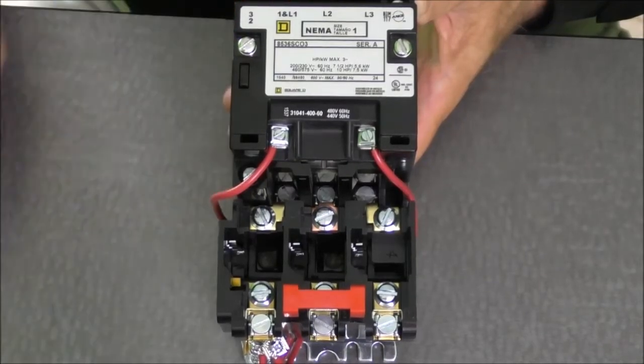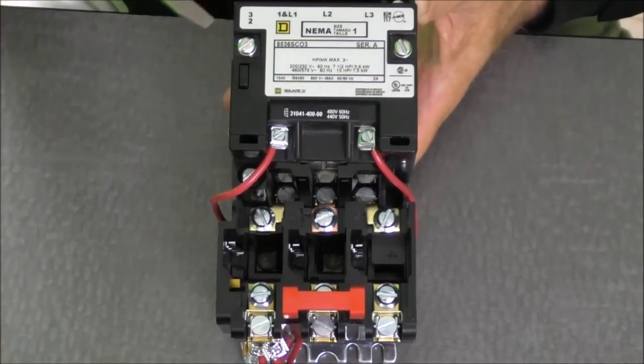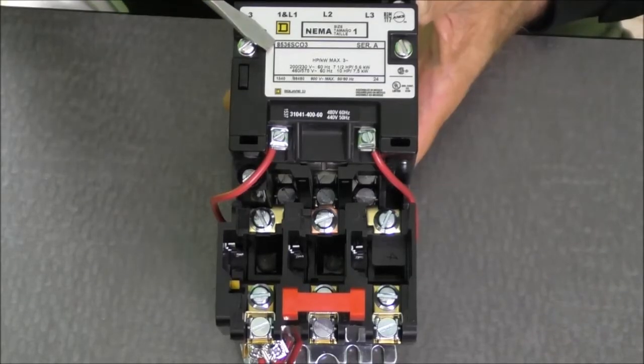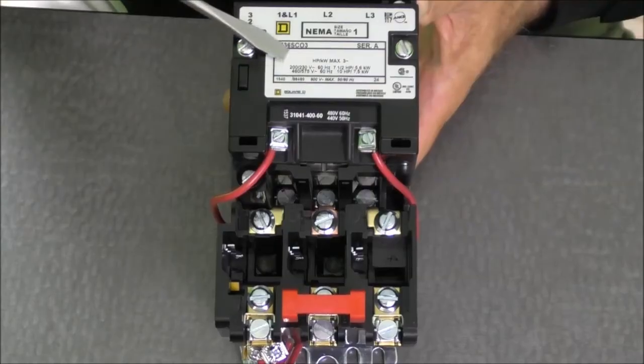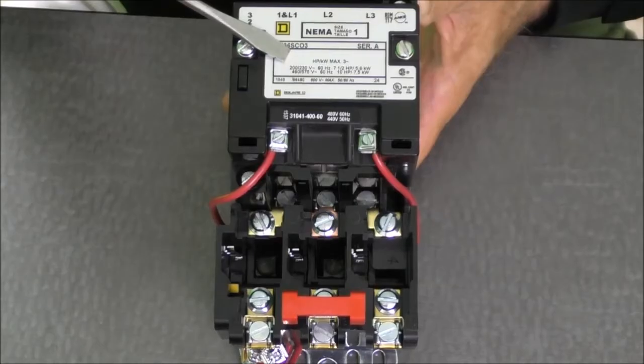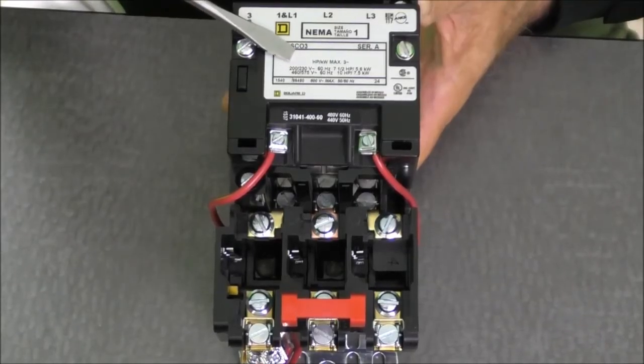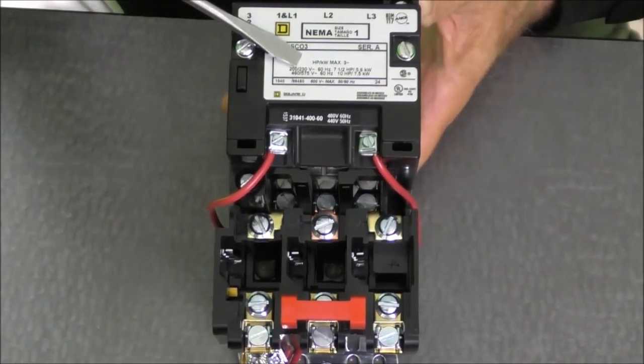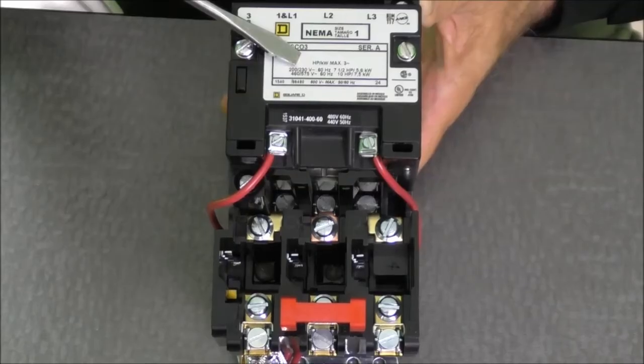It is a NEMA size 1 starter. On the nameplate we can see our catalog number. It begins with an 8536. The first letter after the 6 is an S for Type S. The C will represent a NEMA size 1. The O will tell me that is an open starter.